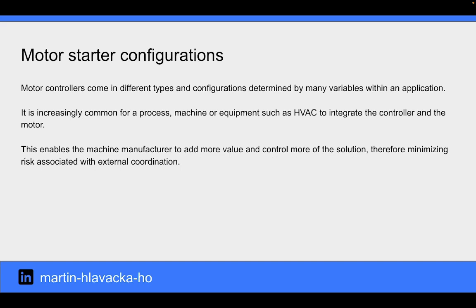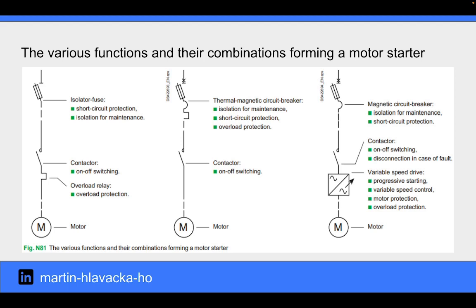Motor controllers come in different types and configurations, determined by many variables within an application. It is increasingly common for a process, machine, or equipment such as HVAC to integrate the controller and the motor. This enables the machine manufacturer to add more value and control more of the solution, therefore minimizing the risk associated with external coordination. In this diagram, you can see the various functions and their combinations forming a motor starter.